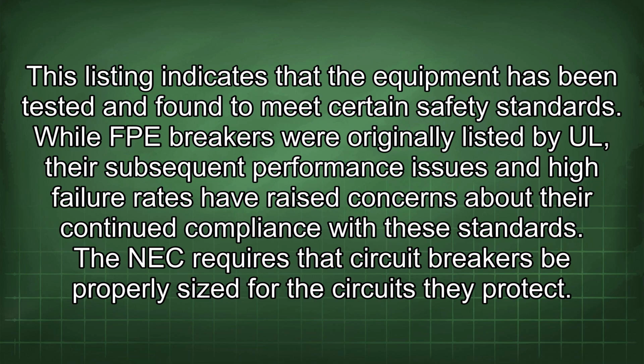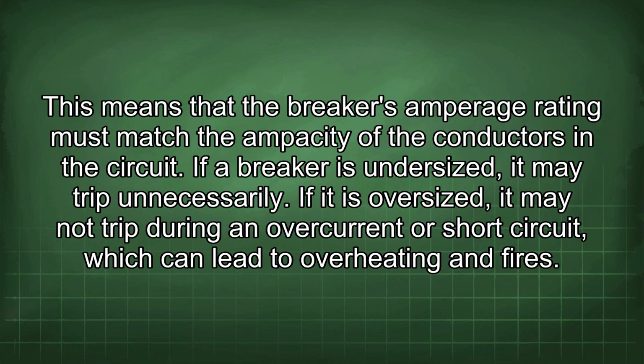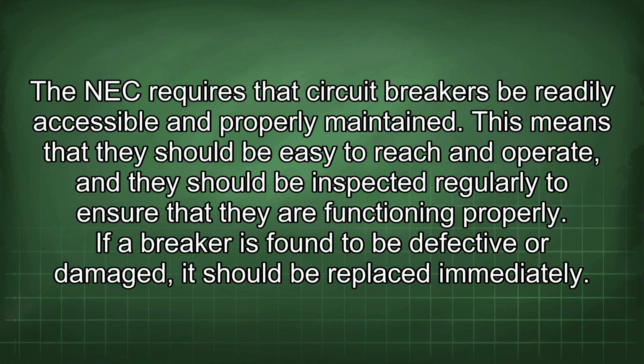The NEC requires that circuit breakers be properly sized for the circuits they protect. This means that the breaker's amperage rating must match the ampacity of the conductors in the circuit. If a breaker is undersized, it may trip unnecessarily. If it is oversized, it may not trip during an overcurrent or short circuit, which can lead to overheating and fires. The NEC requires that circuit breakers be readily accessible and properly maintained. This means that they should be easy to reach and operate, and they should be inspected regularly to ensure that they are functioning properly. If a breaker is found to be defective or damaged, it should be replaced immediately.